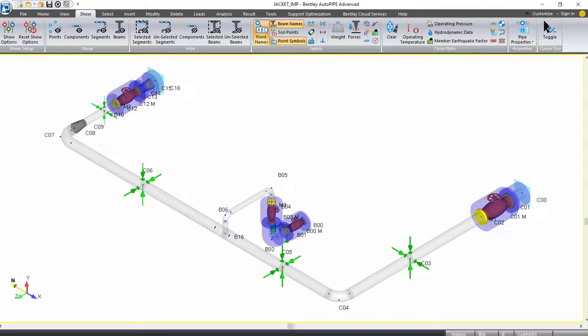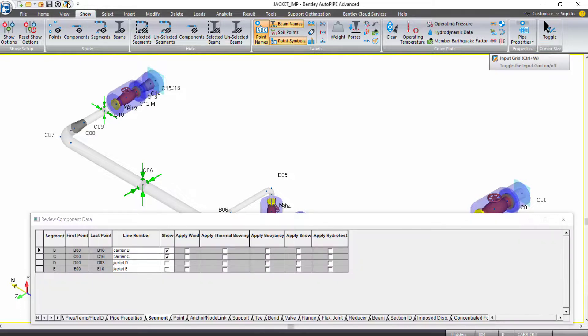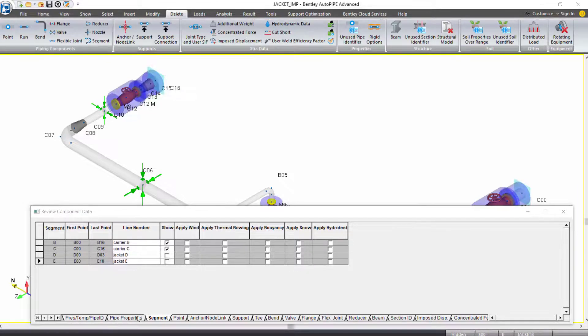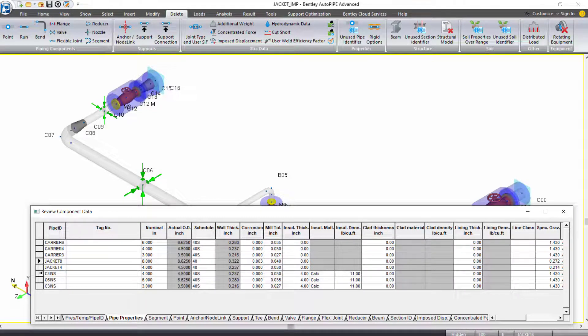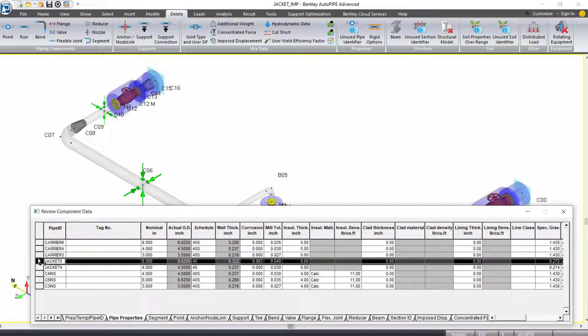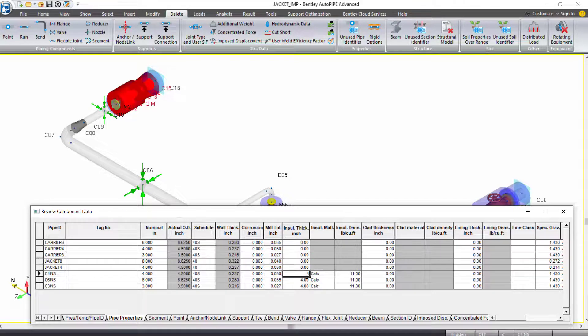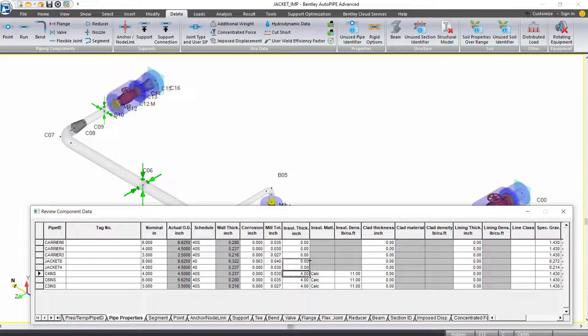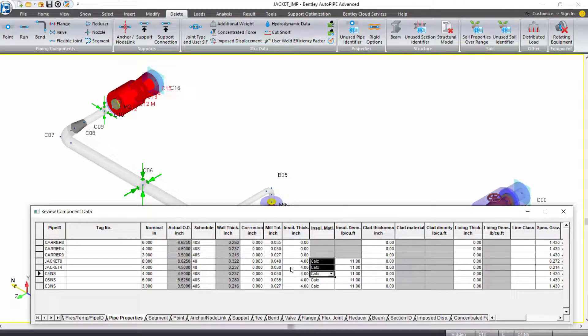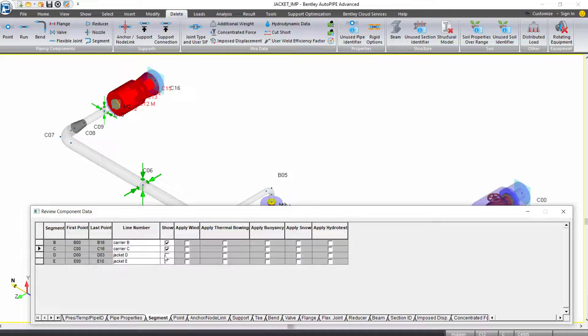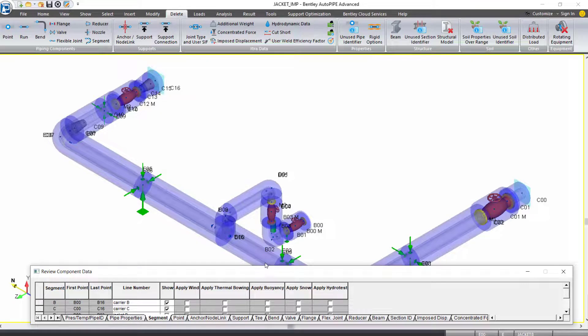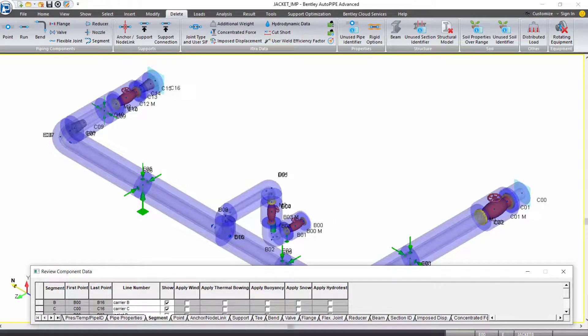We also want to apply the insulation to our jacket piping. Let's open up our input grid. The easiest way to do this is all the jacket piping is assigned a specific pipe ID. If we open the pipe properties tab, we can see the three new pipe IDs for our carrier piping now has insulation applied. We want to apply the same insulation to our two jacket pipe IDs. You can either type them in or drag the information up, just as you would in Excel, to apply four inches of insulation with the calcium silicate material applied for our jacket piping. When you do that, if we come back to our segment tab and we now check show for all of our segments.